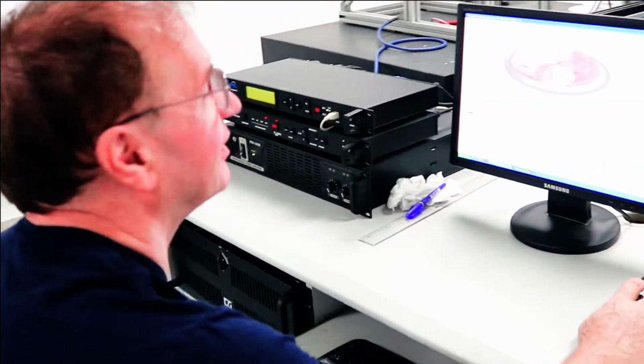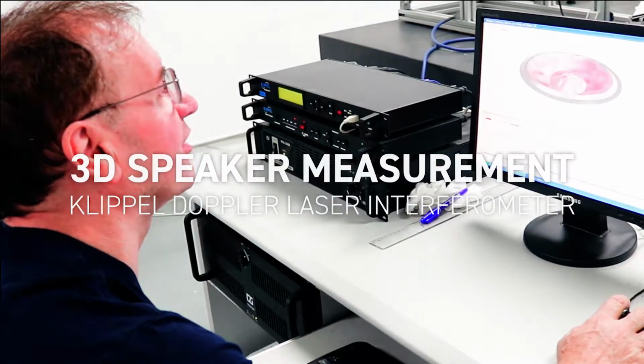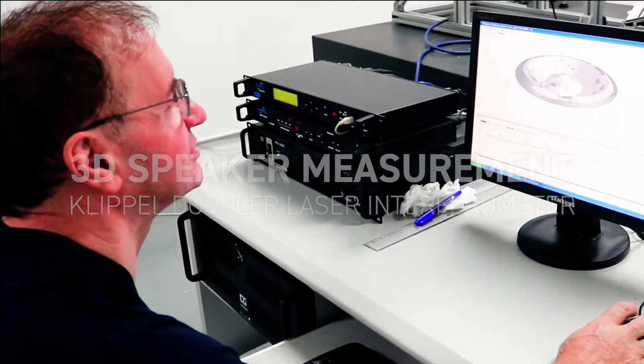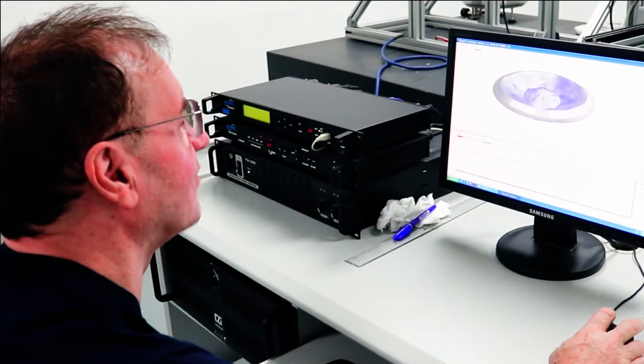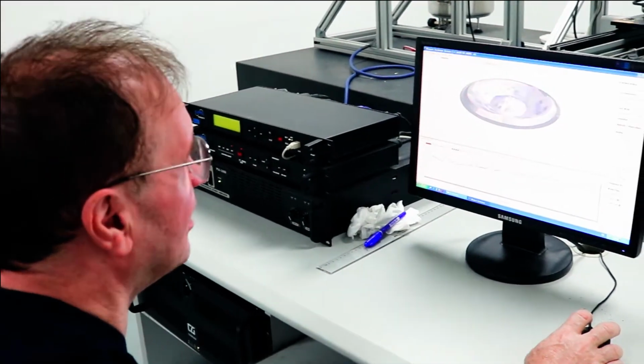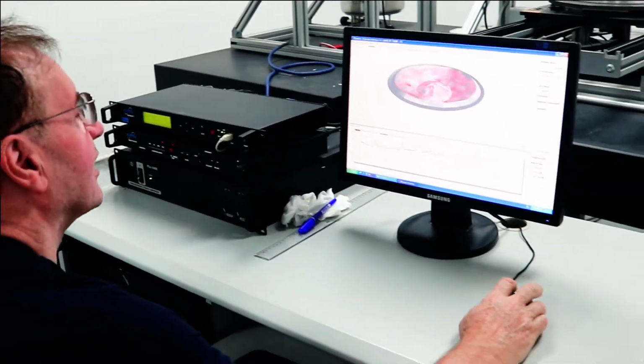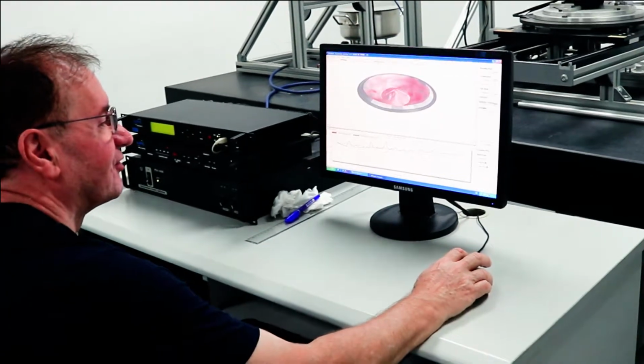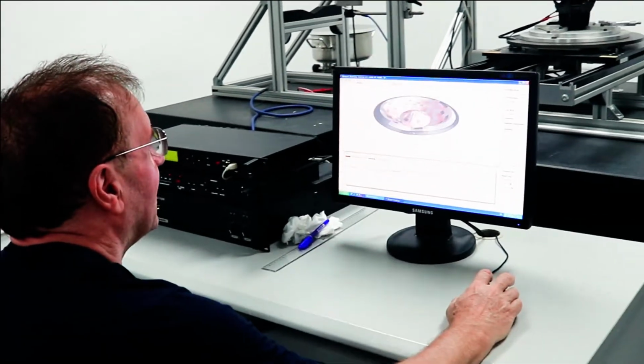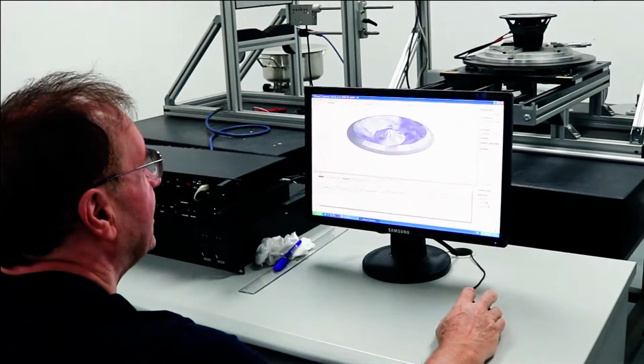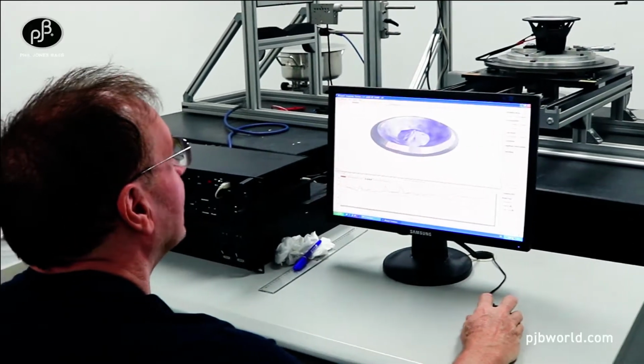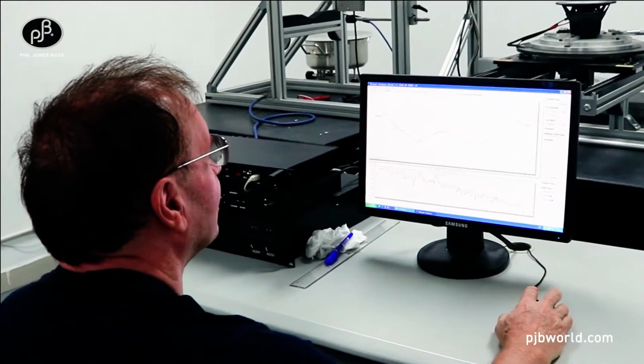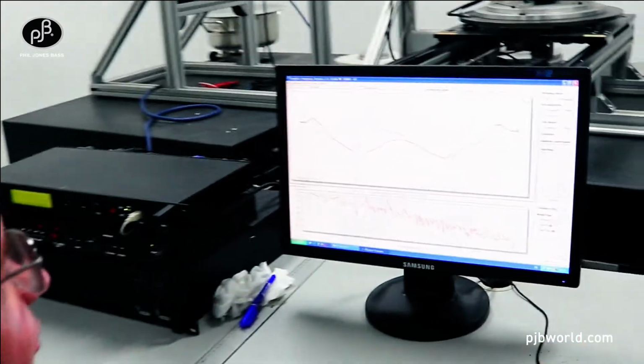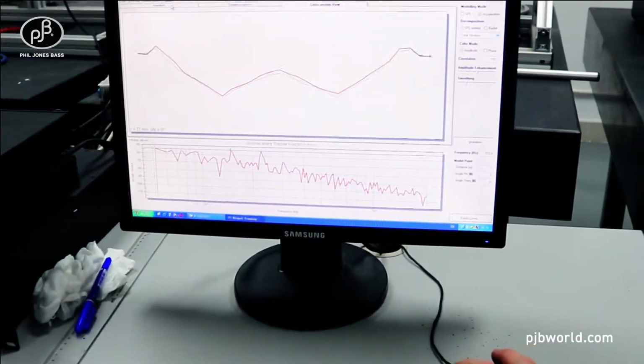This is a laser Doppler interferometer, and we've just done a scan of a 6.5-inch aluminum cone bass driver for the AirPulse Model 2 loudspeaker. This is a frequency of 515.6 hertz, and this is a 3D animation of the cone. We can look at the cross-sectional view to see the dust cap, the surround, and the cone in cross-section.